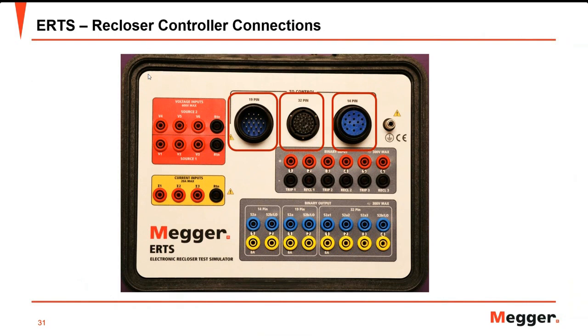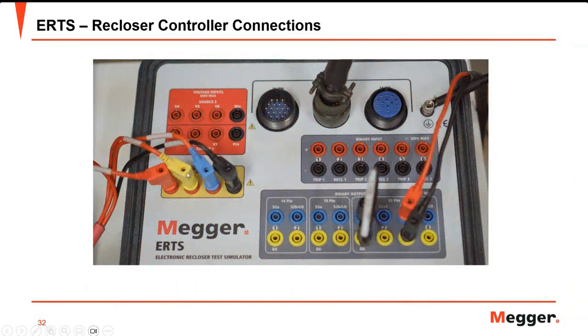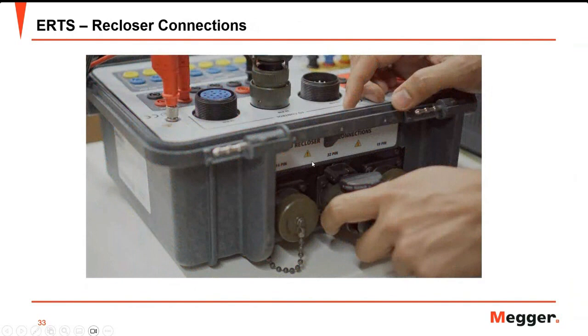Let's check how to connect the Megger relay test system, the SMRT. Here you can see we connected the current for testing the overcurrent functions, and we have connected the binary output of the SMRT going to the 32-pin of the ERTS. The next connection is the recloser connection, which is connected to the recloser unit.